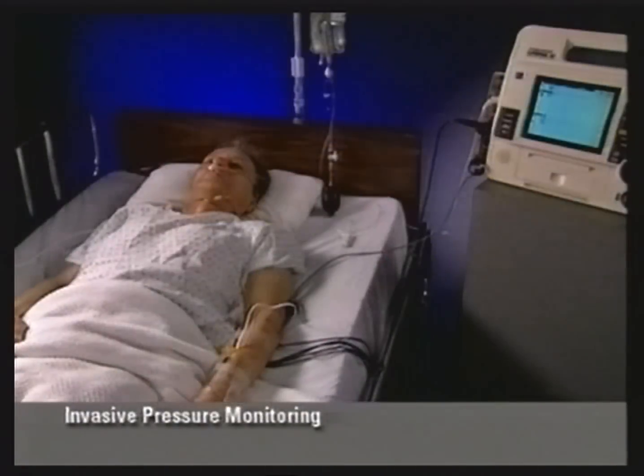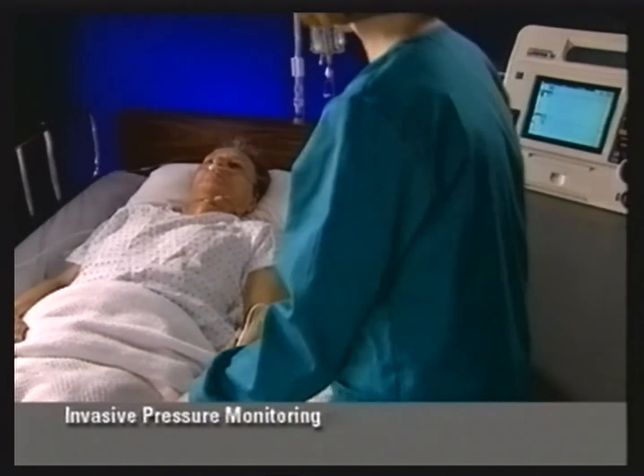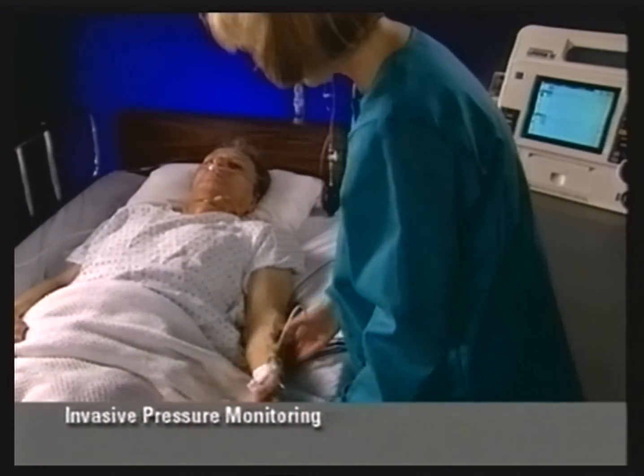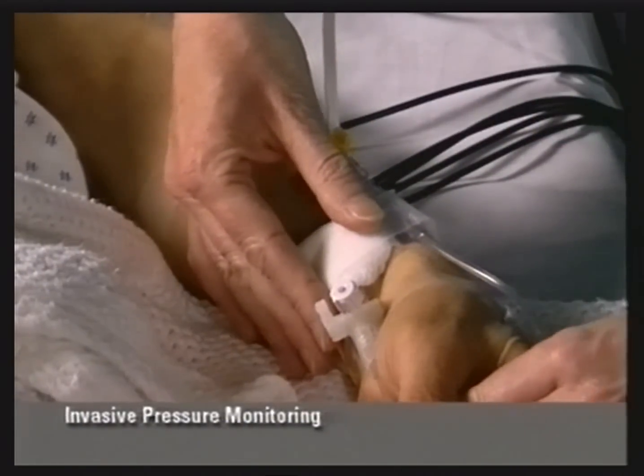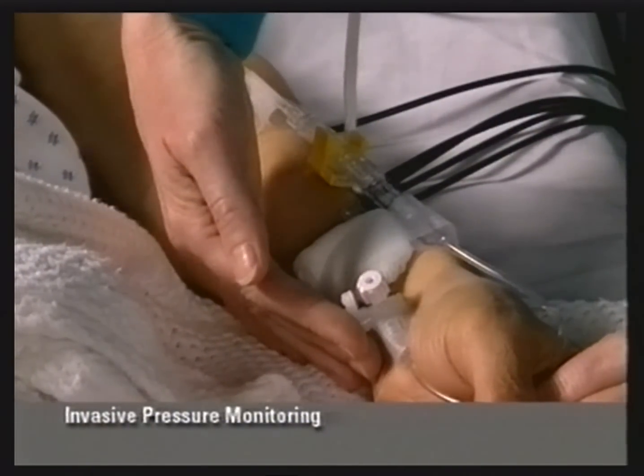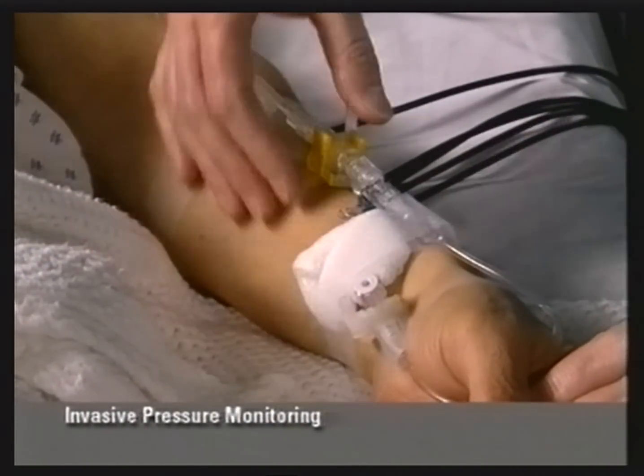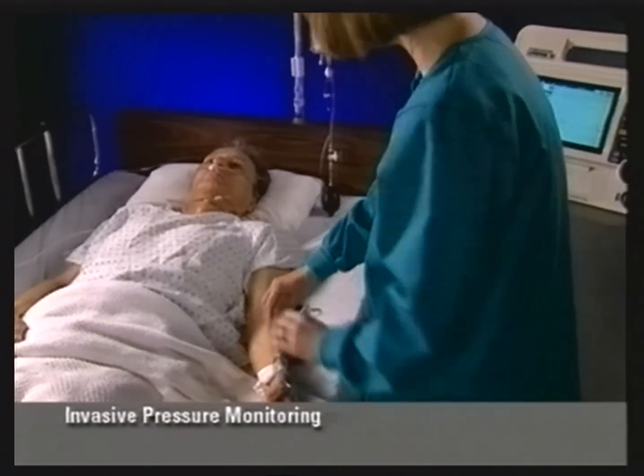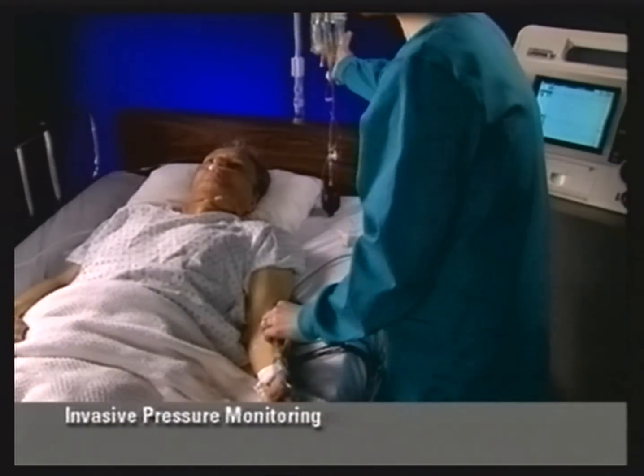The invasive pressure monitor can be used for measuring arterial, venous, intracranial, or other physiological pressures. Invasive pressure monitoring involves the conversion of fluid pressure into an electrical signal. The conversion is accomplished with a pressure transducer. The transducer is connected to a patient's indwelling pressure catheter using a special assembly of tubing, stopcocks, adapters, flush valves, and fluids, commonly known as a flush system.